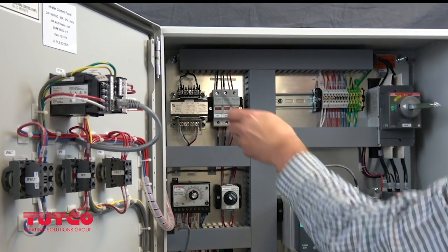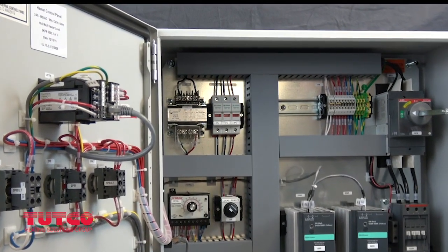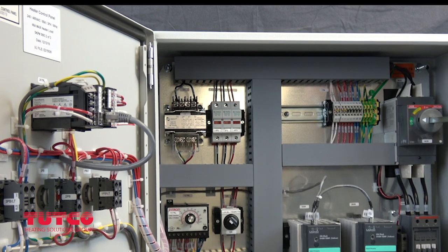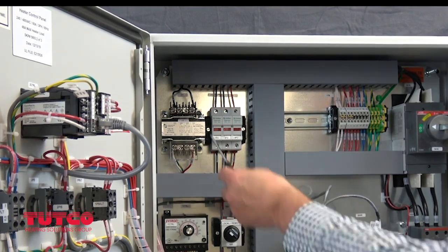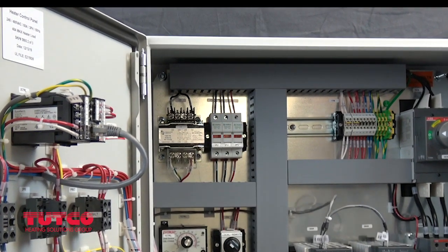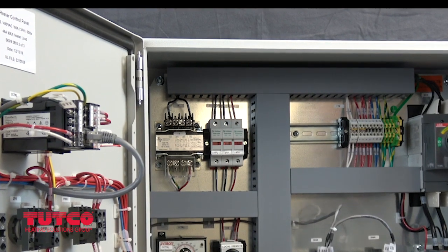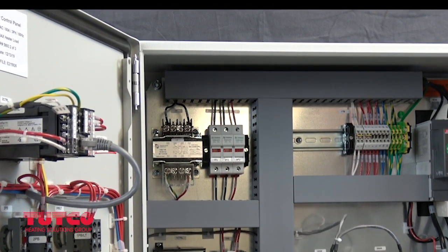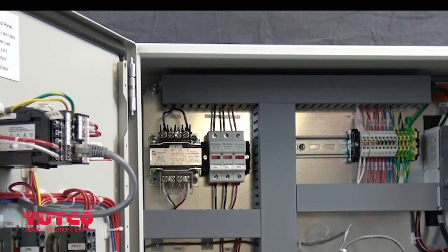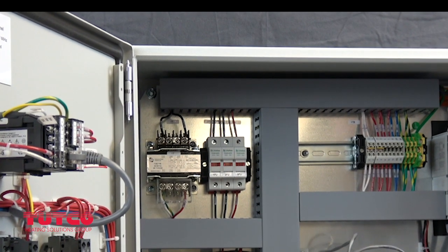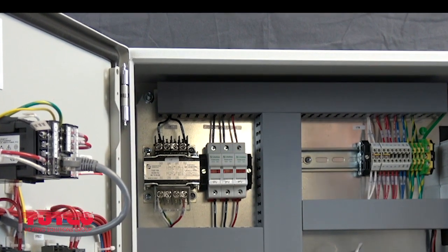There are 4 screws, top and bottom, that wire up both the input and output sides of the transformer. You're concerned with the top. As default, the input jumper is connected to the middle 2 screws labeled 3 and 2 for 480 volt power line connections. We're now going to change the 240 volt input wiring jumpers.